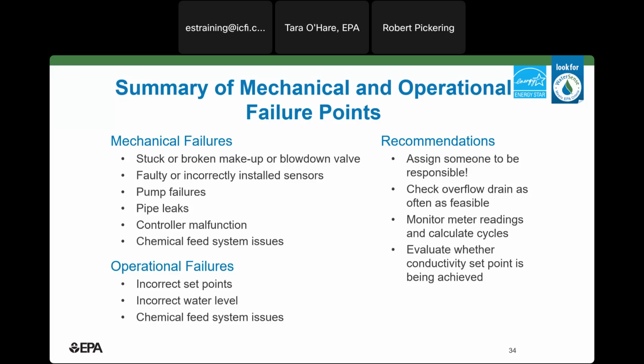Faulty sensors can have similar repercussions. If the conductivity or the level sensor isn't communicating correctly with the controller or blowdown valve, you could be blowing down too much or too little. Like any system, there's a potential for pumps to fail or pipes to leak. And then lastly, controllers, either for conductivity or a chemical feed system, can malfunction and again result in the tower blowing down too often or not enough.